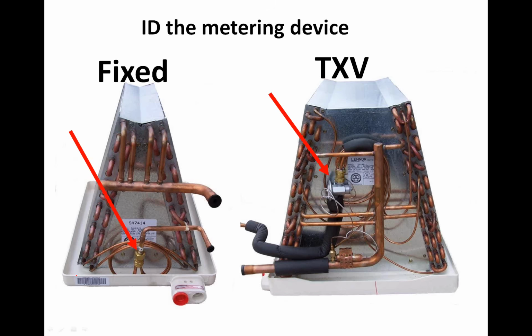We talk about IDing the metering device. Okay, it's critically important when you charge a system that you know what type of metering device you have. And the one on the left is a fixed orifice. And a fixed orifice has got inside that brass nut, you'd see a small piston. I have a picture in a slide coming up. Or on the right, we have a TXV, a thermostatic expansion valve.